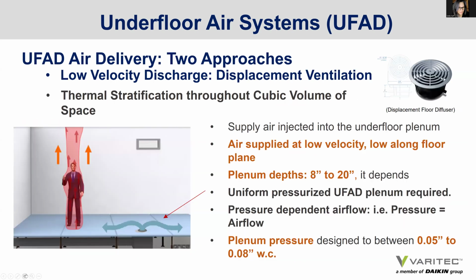Then for displacement ventilation, less air is supplied through each diffuser. The same principles apply with regard to plenum pressure, so there's no advantage or disadvantage there. Plenum heights are the same. The difference is that the whole space from the floor to the ceiling is thermally stratified. One could argue, does it offer a level of better indoor air quality? Conceptually, possibly. I've not seen any papers or studies that made a comparative evaluation between semi-turbulent and displacement ventilation floor diffusers.